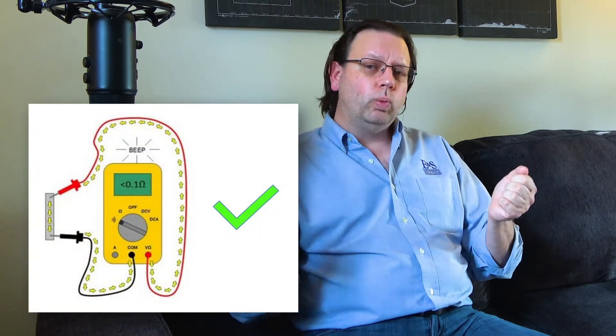You can even check the chassis of objects, the transformer or the switches that may be in the yard to make sure that those are bonded. If we find that some metallic object does not have a low impedance fault current path back to our source, we know that that's an area that voltages can form. They're going to be higher than the surrounding other metal parts. That's a risk for human beings, and that's exactly what we're looking for when we're doing this is for high resistances. Anything above... And what you're looking for generally in continuity is something really, really low, like 0.1 ohms or less kind of thing. We want to have a nice low. We want it to be solid metal, well connected.